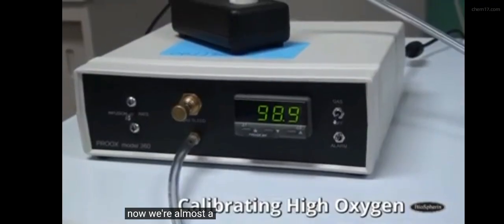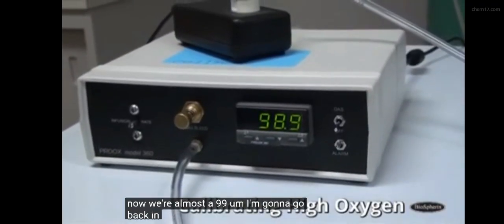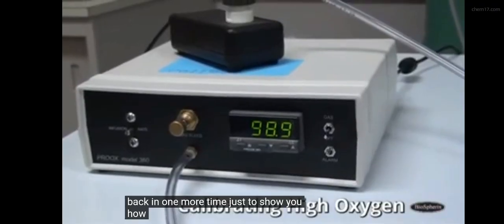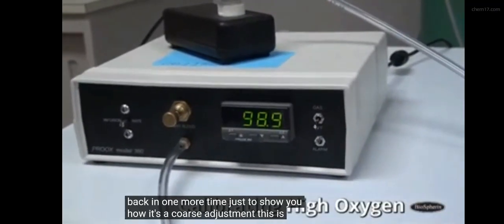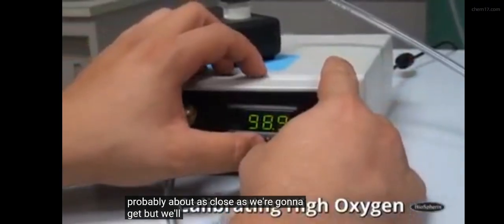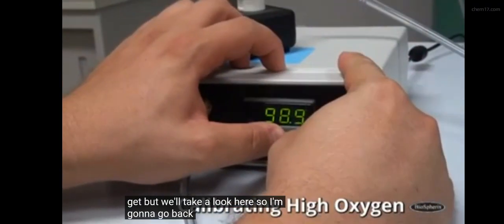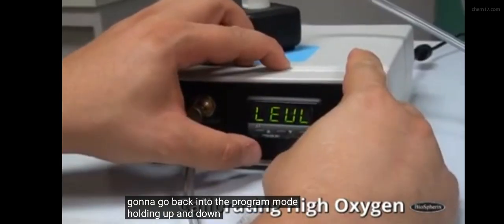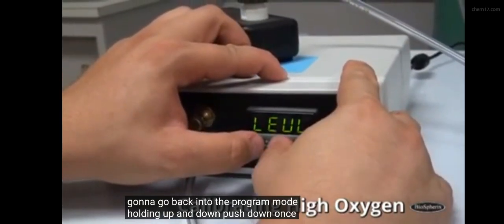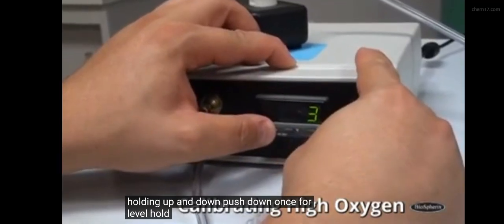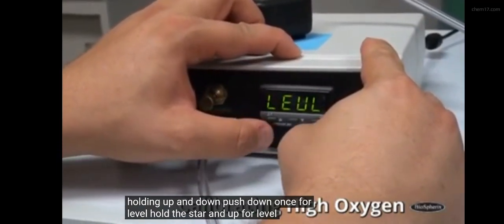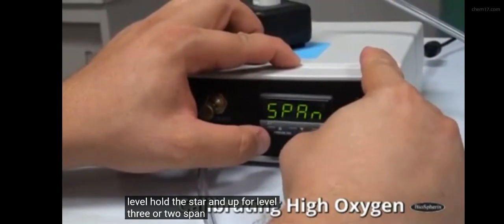Now we're almost to 99. I'm going to go back in one more time just to show you how it's a coarse adjustment. This is probably about as close as we're going to get, but we'll take a look here. So I'm going to go back into the program mode, holding up and down. Press down once for level. Hold the star and up for level 3. Over to span.